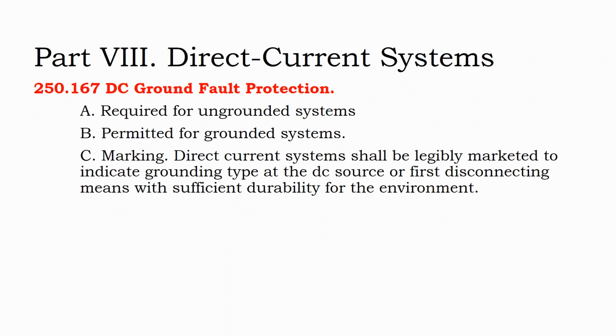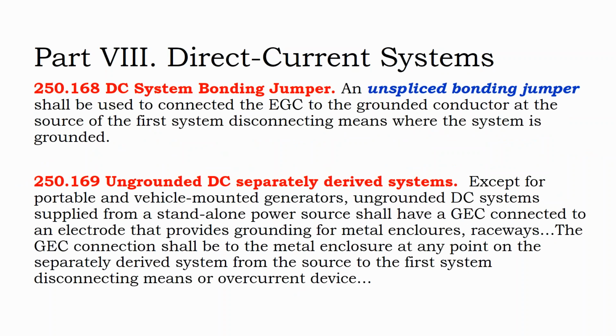Let's see. DC ground fault protection is required, and we've talked about how it used to be connected to the grounding system, creating a blind spot. An unspliced bonding jumper shall be used to connect the equipment ground conductor to the grounded conductor at the source of the first system disconnecting means. And so from the DC solar disconnect up to the roof, let's see, ungrounded DC systems supplied from standalone power sources should have a grounding electrode conductor connected to an electrode that provides grounding for metal raceways. All right, so you need to be grounding your systems at the source to the first disconnecting means.